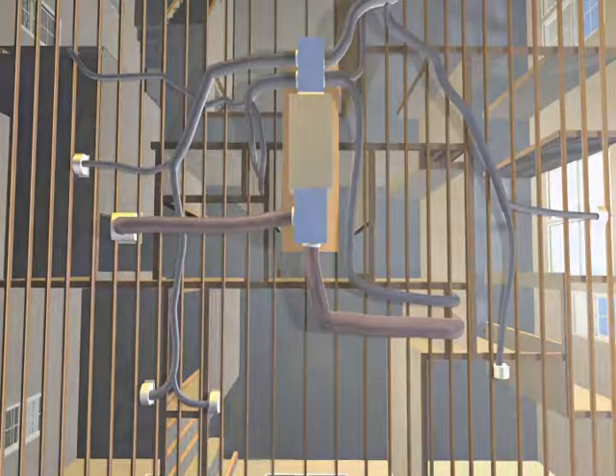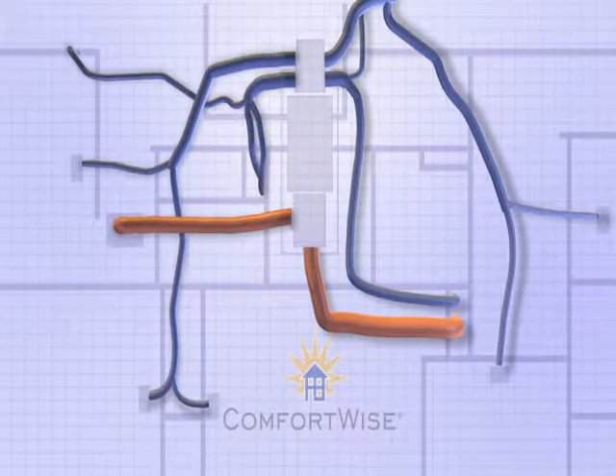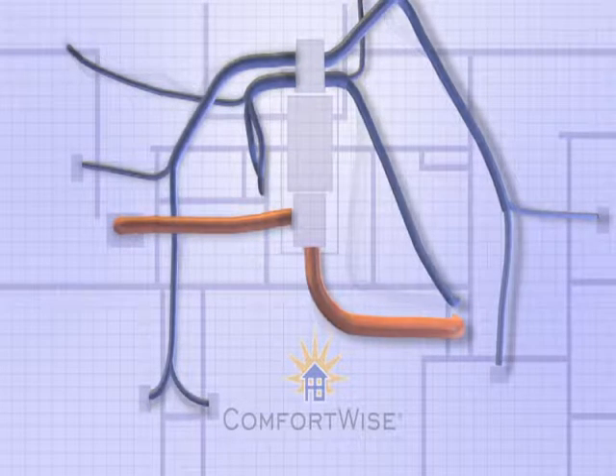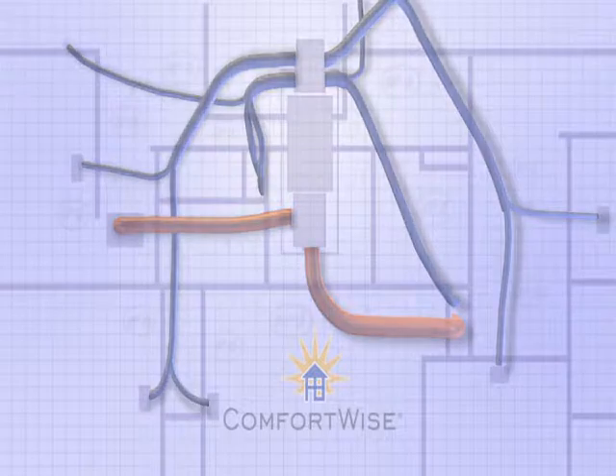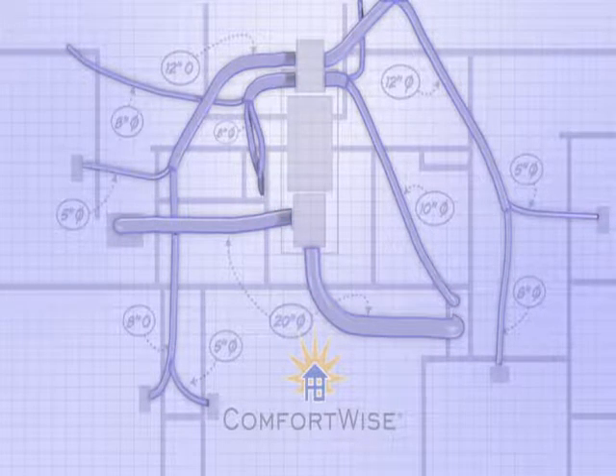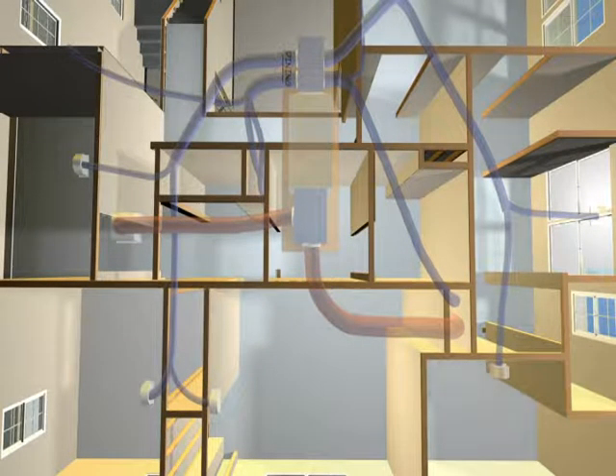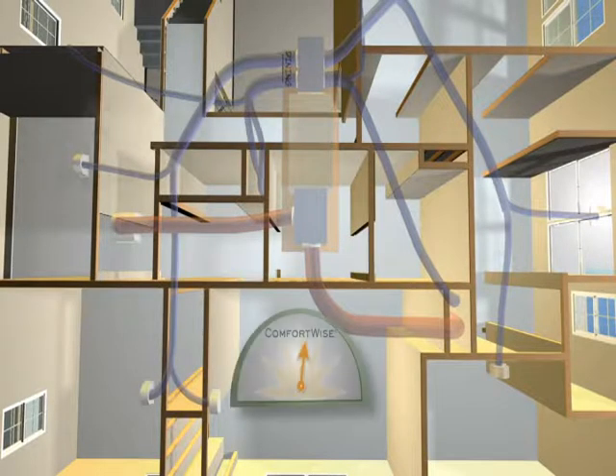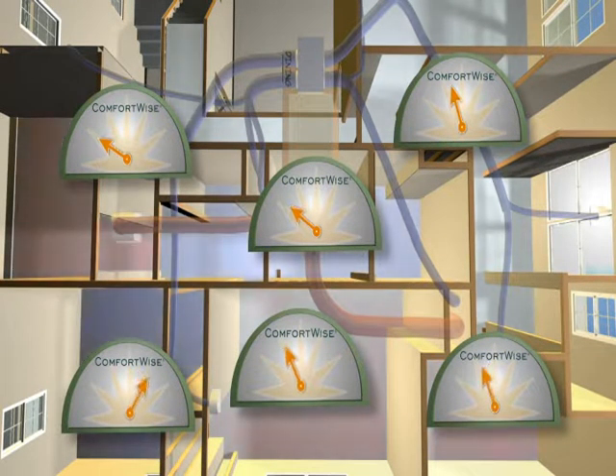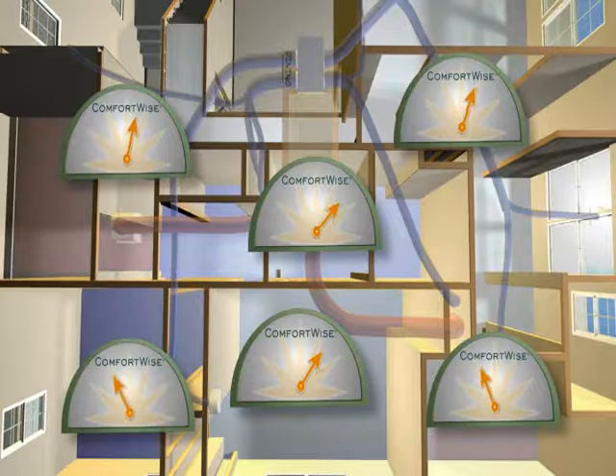The second factor has to do with ducts. The length of the duct run is important, plus minimizing sharp bends that can reduce airflow, and the ducts need to be the right size as well. We perform room-by-room heating and cooling load calculations, a very important tool to determine the right size duct for each room or area.